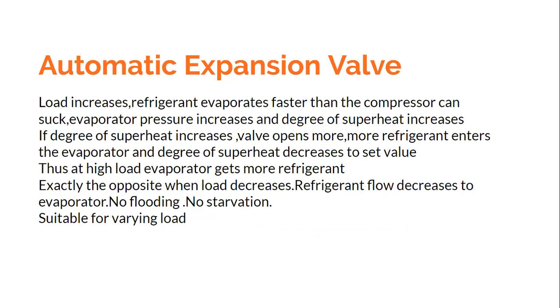So how does it behave? Again, I'm saying that this is not the automatic expansion valve. We are talking about the thermostatic expansion valve. So how does this behave? This thermostatic expansion valve also behaves with respect to load changes, but it behaves very intelligently, unlike the stupid behavior of the automatic expansion valve. What is the stupid behavior of the automatic expansion valve? In the automatic expansion valve, with an increase in the load, actually the evaporator starves, and with a decrease in the load, the refrigerant in the evaporator increases, and the evaporator floods. So that is not desirable.